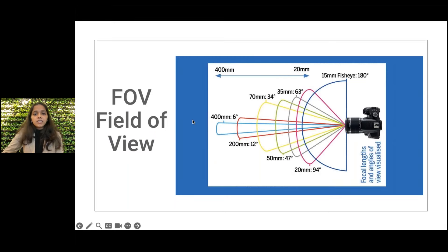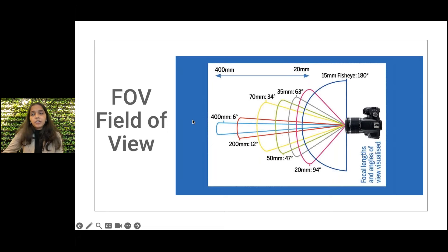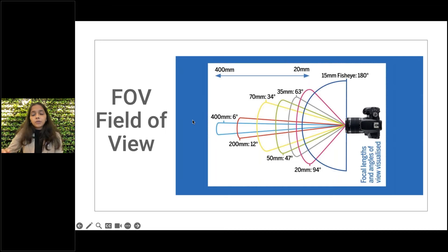Scan depth refers to the range or distance at which the scanner is capable of capturing details in the oral cavity — in simpler terms, how deep your scanner can go into the oral structures effectively. Think of FOV (field of view) in a camera: the scan depth in an intraoral scanner is the depth or distance the scanner can capture in one single frame. Scan depth is calculated from the tip of the scanner to the object or surface of the tooth.